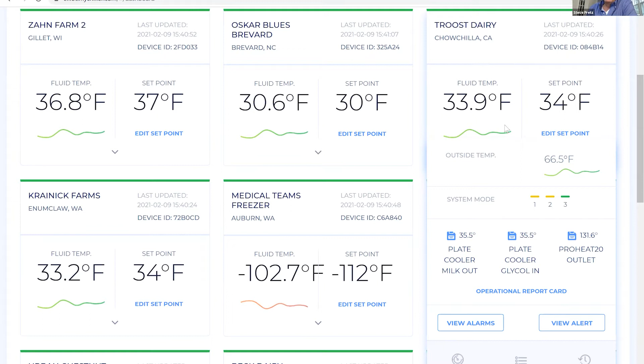The main thing we're concerned about on any dairy farm chiller is the fluid temperature. The chilled glycol solution, this system is set up to maintain 34 degrees. We're within 1/10 of a degree now. You also see the outside temperature. That may not be the weather guy's temperature. It's the local temperature of the chiller. And that's important to remember.